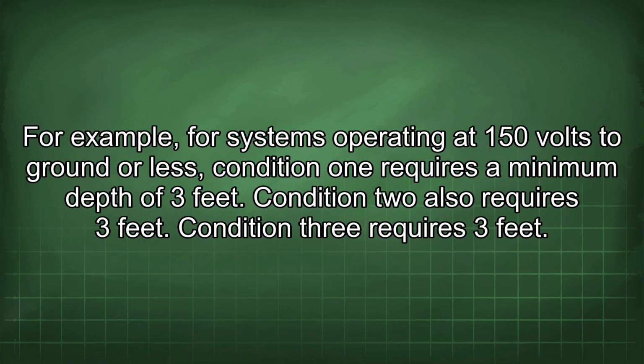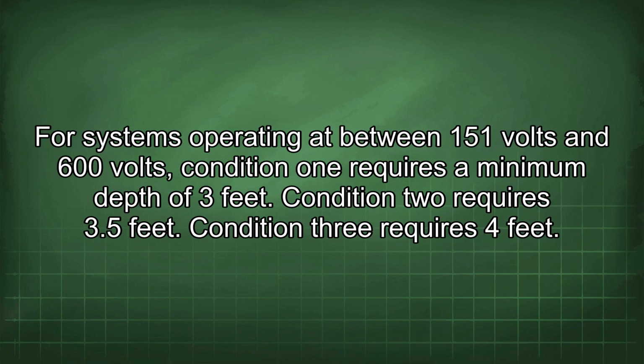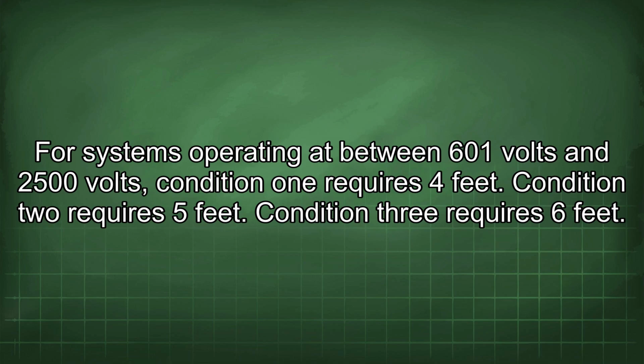For example, for systems operating at 150 volts to ground or less, Condition 1 requires a minimum depth of 3 feet. Condition 2 also requires 3 feet. Condition 3 requires 3 feet. For systems operating at between 151 volts and 600 volts, Condition 1 requires a minimum depth of 3 feet. Condition 2 requires 3.5 feet. Condition 3 requires 4 feet. For systems operating at between 601 volts and 2500 volts, Condition 1 requires 4 feet. Condition 2 requires 5 feet. Condition 3 requires 6 feet.